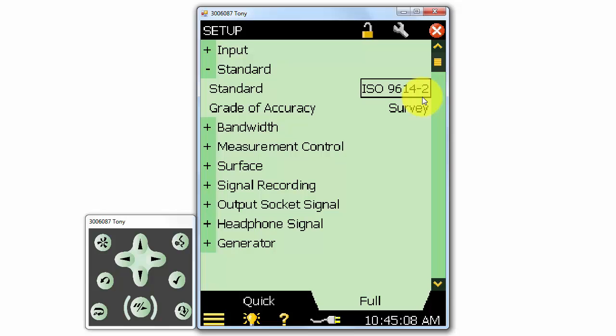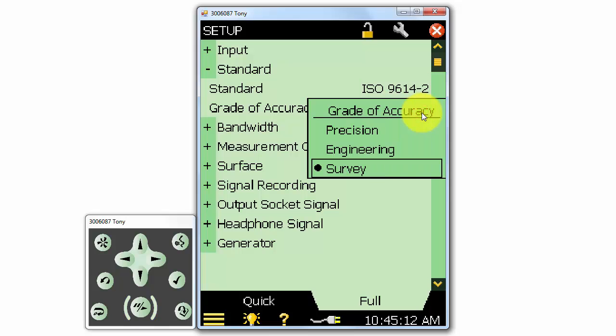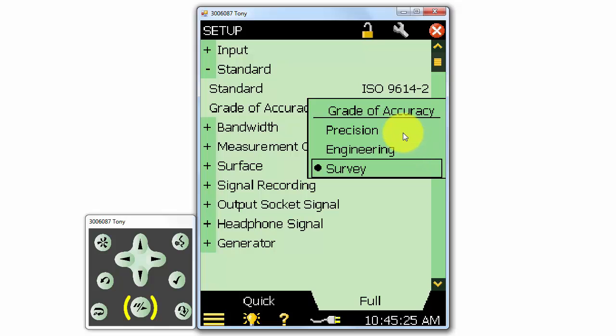There are different grades of accuracy that we can select: survey, engineering, and precision grade. The test methodology is generally the same for all three, but the tolerances for repeatability and other factors are tighter as you move to engineering and then to precision grades. For this demonstration, I'll select survey.